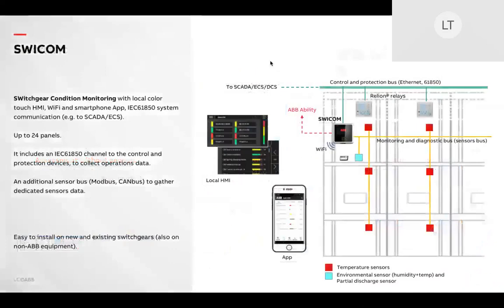So, how do we collect all the data to get to one holistic view? The answer is SWICOM. It's one device mounted to your switchgear, exactly as a relay, that all your relays and sensors connect to. SWICOM will collect data from not only ABB assets, but also from non-ABB assets. SWICOM can be considered to be applied in layers. It can take data from your relays, for example, open and close times, number of operations, number of short circuit actions, etc. You might ask, why use SWICOM for this if my relay has the data?